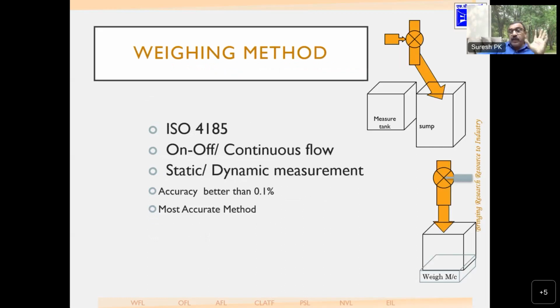So now the weighing method. The weighing method is based on ISO 4185. You can use on-off flow or continuous flow. You can use static or dynamic measurement, with accuracy better than 0.1%. It is supposed to be the most accurate method.